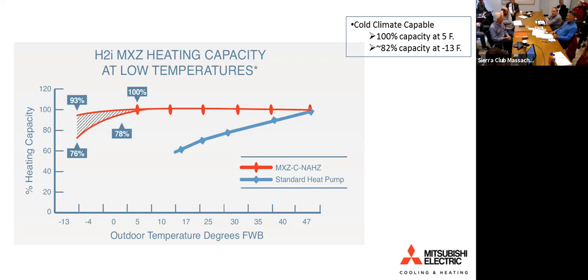At -5 degrees, how does this efficiency compare to that of a geothermal system? At those lower temperature bins, geothermal is typically more efficient because it's getting its heat from a constant 50-degree source, always a constant source. This system is getting its heat from the air, so it's derating as you go, but it's no longer derating along this line, it's derating just over here.